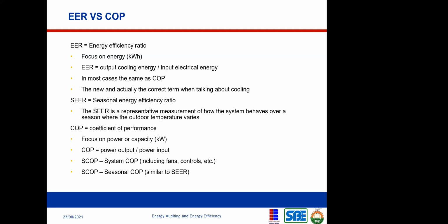So EER versus COP. Basically, the long and short is that EER is mostly for air conditioning, for cooling, while COP is for heating.